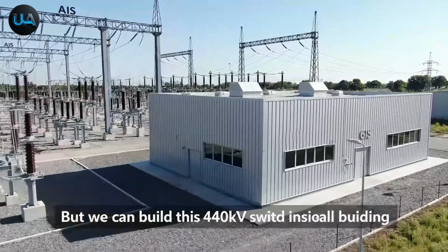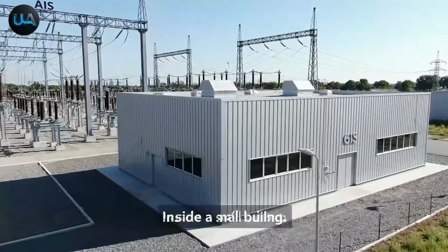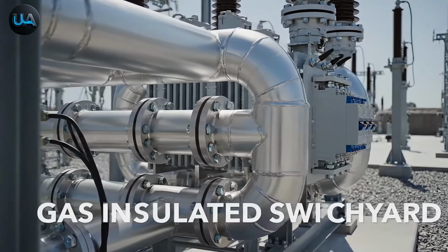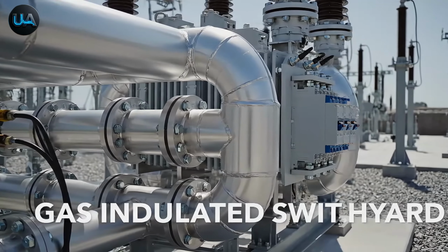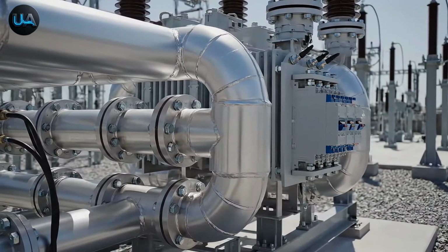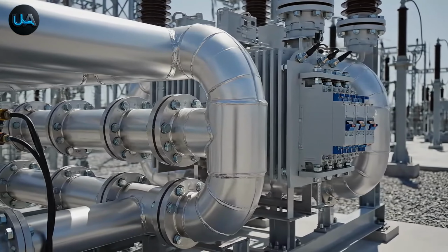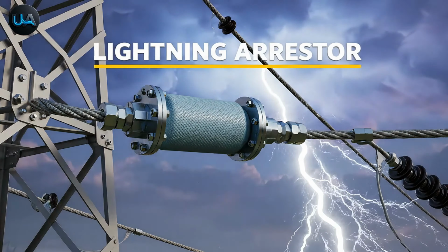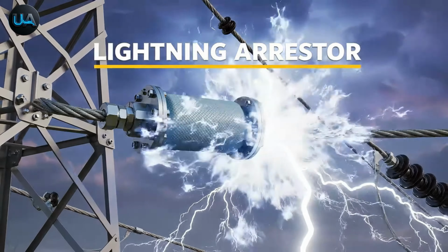But we can build this same 440 kilovolt switchyard inside a small building. The only difference is that instead of air, we must use gas insulation. This is called a Gas Insulated Switchyard, or GIS. The incoming line first has a lightning arrestor, which protects the system from overvoltage surges.